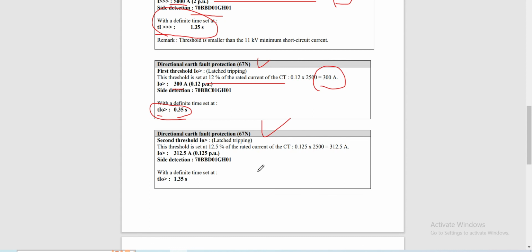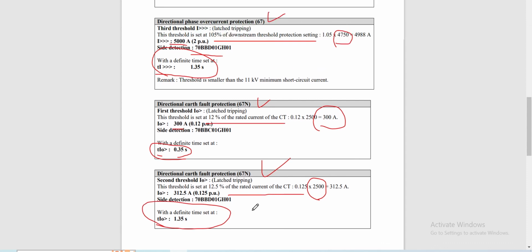Our second threshold is on the opposite direction. This threshold is set at 12.5% of the rated current of the CT, so we multiply 0.125 times 2,500 for the CT. That's why our second threshold is set at 312.5 ampere, or 0.125 per unit, with a definite time set at 1.35 seconds. So our time setting for the earth fault protection is the same as for our phase overcurrent protection. We have done our phase overcurrent and earth fault protection.